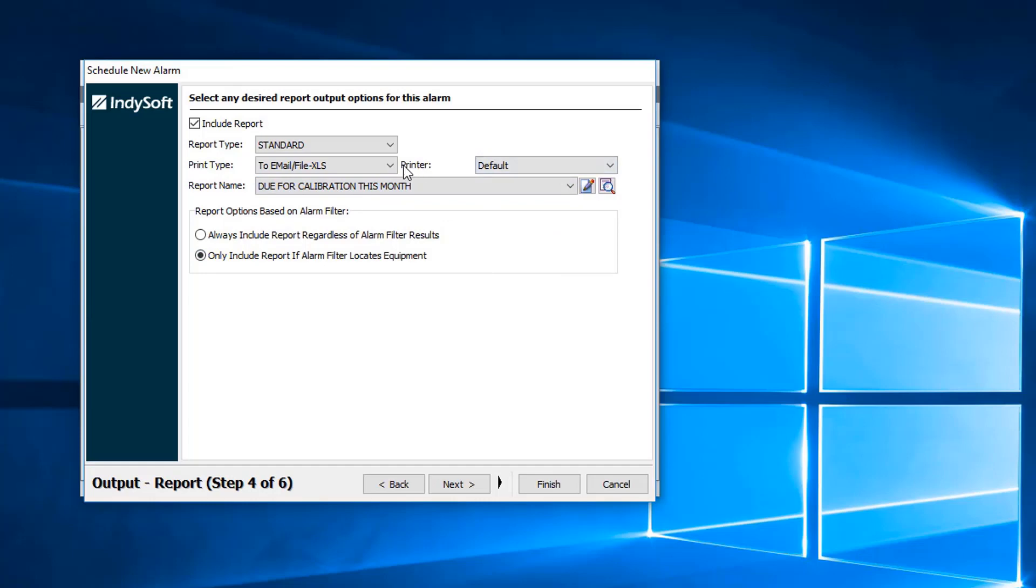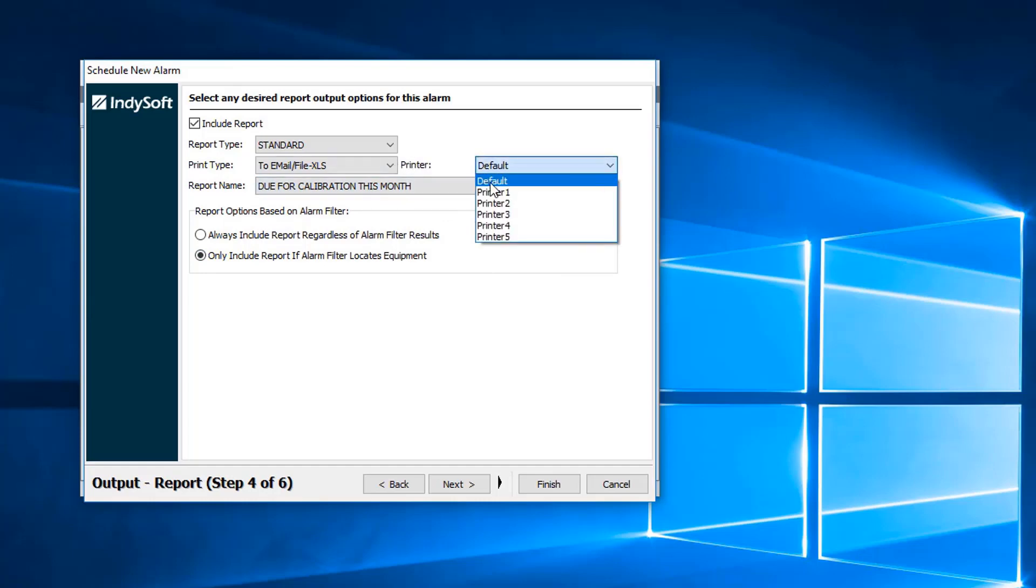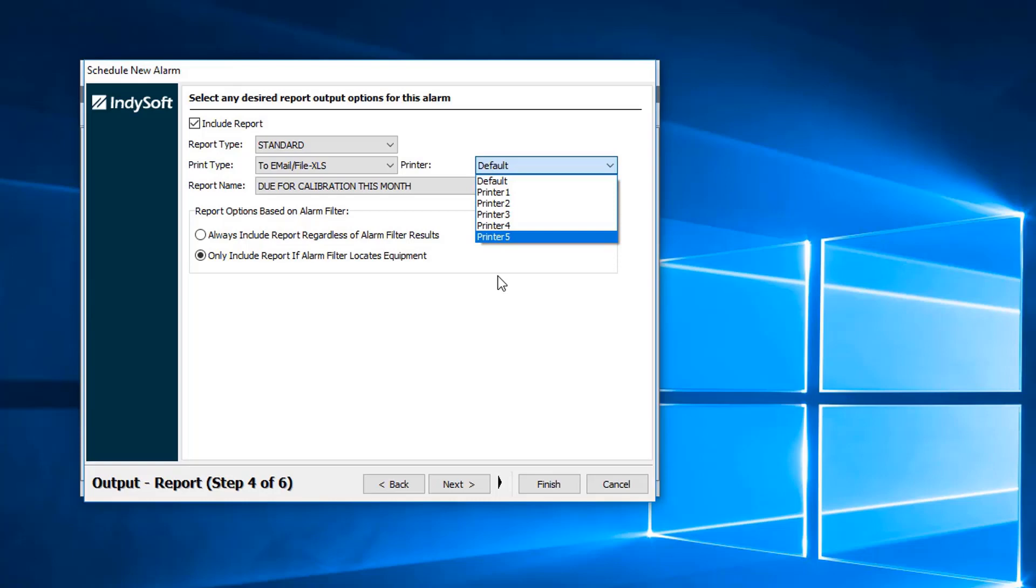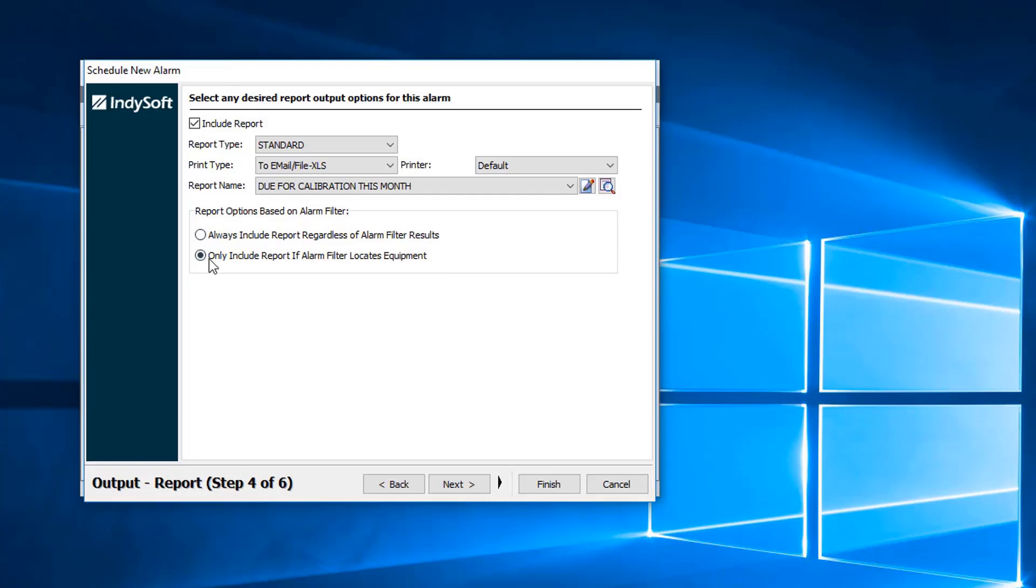Next, we go to our report names and we will just do our due for calibration this month. Over here we do have the printer section so we can send it to the default printer or printer one through five that would be set up in your user location settings. We have the report options based on alarm filter.